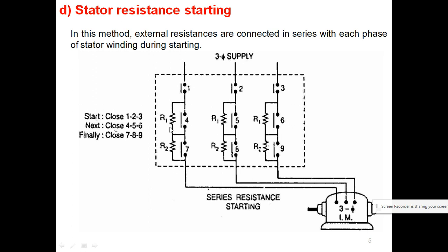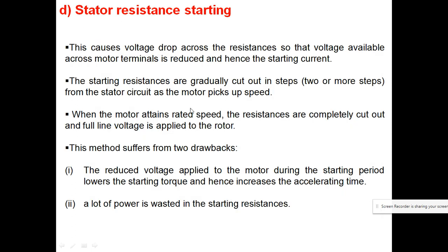So it means this resistance has been removed from the circuit, and now the three phase supply is going directly to our starter. In this way we can use this starter. The voltage drop across the resistance means the available voltage across the motor terminal is reduced, hence the reduced starting current. Then we cut out the resistance in one or two more steps, and when the motor attains rated speed, the resistance is completely cut out and full line voltage is applied to the motor.